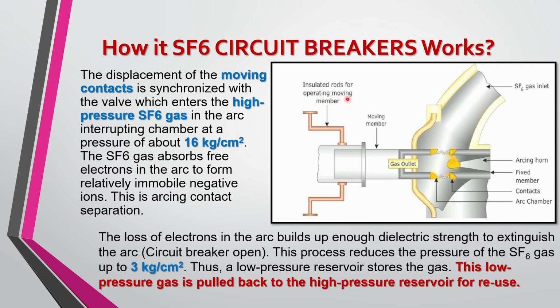So insulating rods are for operating or moving the moving member. So these are the contacts. This one is a contact. This one is a contact, and arcing horn. In the middle of these two contacts, basically we have an arcing horn. So the arc chamber is this. This entire whole thing is called the arc chamber, and SF6 gas is pushed from this direction to quench the arc. So the picture itself is self-explanatory, and in the subsequent slide we will see, with the help of animation, how this entire thing happens. The displacement of the moving contacts is synchronized with the valve which lets the high pressure SF6 gas into the arc interrupting chamber at a pressure of about 16 kg per centimeter square.